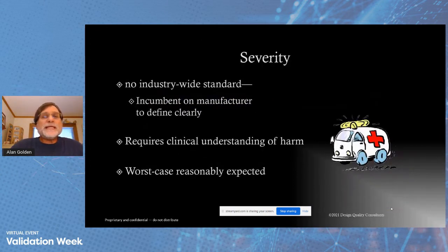So severity, there is no industry-wide standard. You can't open up a document and say, well, if this happens, this is the severity. It is incumbent on the manufacturer to define this clearly. And since severity tends to be a medical issue, you've caused harm to someone, you're probably going to want to have that either decided on or looked over by someone in the medical field. Hopefully you've got someone who's got an MD on your staff, or someone you can have as a consultant who can sign off on that documentation to say, yes, if this happens, this is the medical severity. It does require that clinical understanding of harm.